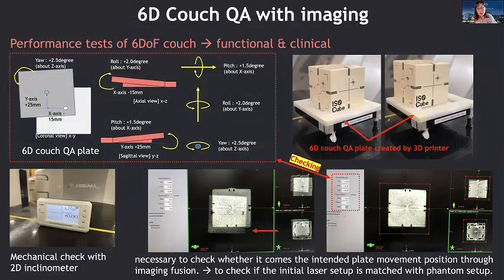Since we are all using image-guided radiation treatments, we rely on image quality and 6D couch movements a lot, so we need to check the 6D couch performance. We benchmarked the commercial phantom and a 6D couch QA plate generated by 3D printers. The mechanical part is checked simply by a 2D inclinometer, and the phantom is used for the imaging QA. For imaging-based QA, it is necessary to check whether the plate movement comes out as intended through the imaging fusions, after applying the movement of the 6D couch based on this number here, and to check if the initial laser setup matches the phantom setup. So this is how we are doing the 6D couch imaging QA at the moment.